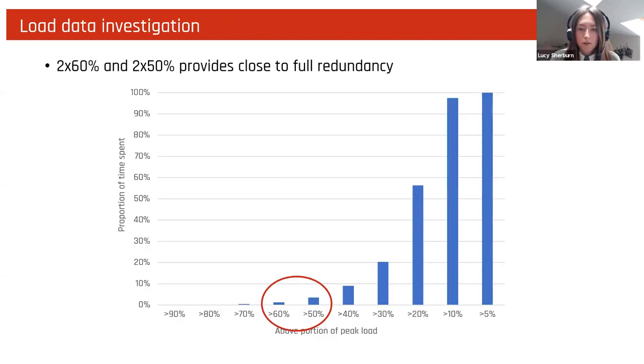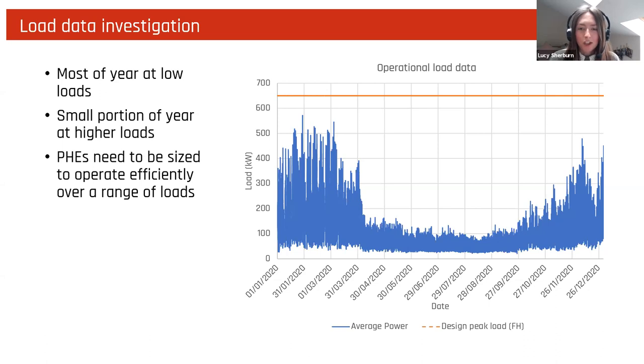So if we take a look at load data, we can see why this is the case. This is operational load data from a site across the year of 2020. The design peak load can be seen by the orange line at the top. Then you can see the power across the scheme. We can see that for large portions of the year, you're operating at quite low loads. And you are getting close to peak load during winter, but not necessarily hitting that. So the takeaway from this is that your plates really need to be sized to operate efficiently over a range of loads. If you have a plate that is sized at peak load and you're only operating at 10, 20% of that, you're going to start seeing that laminar flow and a reduced amount of turbulent flow.